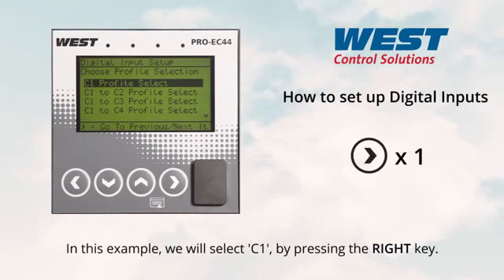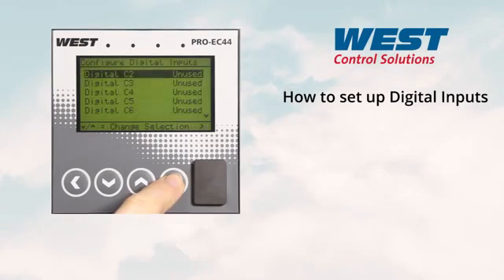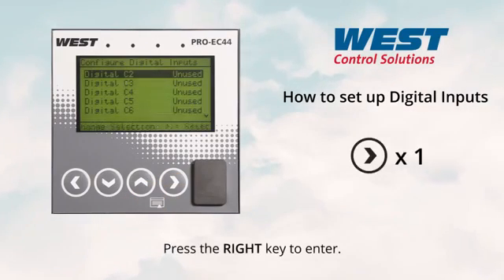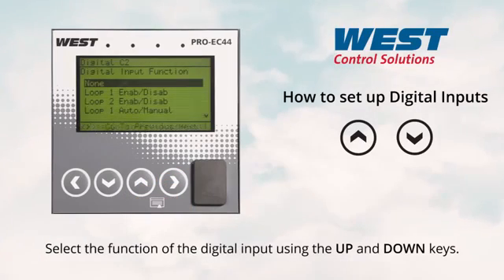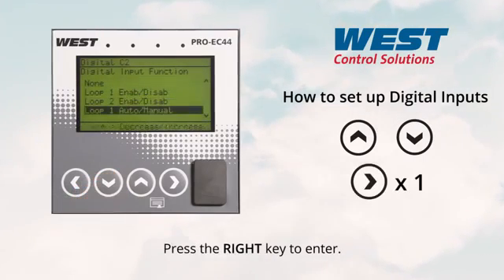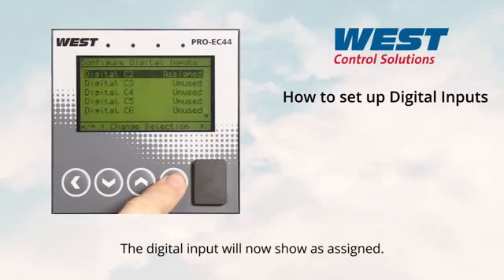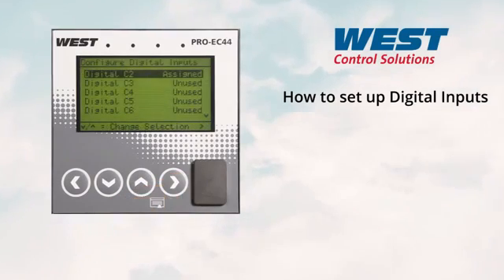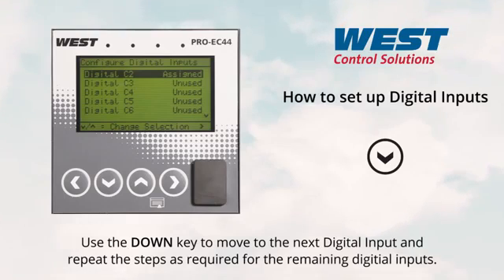In this example, we will select C1 by pressing the right key, then press the right key to enter. Select the function of the digital input using the up and down keys, then press the right key to enter. The digital input will now show as assigned. Use the down key to move to the next digital input and repeat the steps as required for the remaining digital inputs.